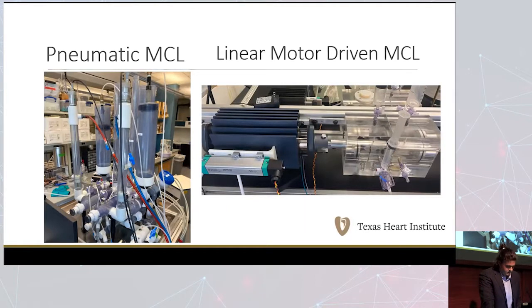And right now, this MCL simulates the left ventricle, left atrium, and systemic flow. So it's more of a mock left heart at the moment. And we've connected this to the vascular structure. And we actually have both MCLs in the back on display if anyone is interested.